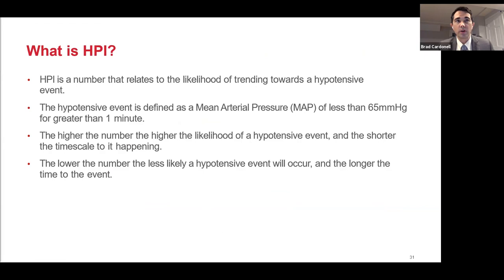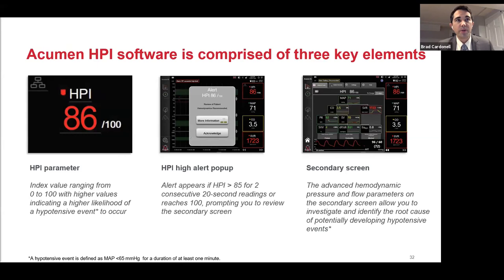HPI is a number that relates to the likelihood of trending towards a hypotensive event, defined as MAP less than 65 for greater than one minute. The higher the number, the more likely the hypotensive event and the shorter the time until it occurs — and conversely, the lower the number, the less likely or the longer until an event. Acumen HPI software has three key elements: the HPI number (a value from 1 to 100), the HPI pop-up alert (which appears after two consecutive readings above 85), and the secondary screen which provides further details about the potential causes and treatments of the hypotensive event — allowing us to get at the root cause rather than just temporizing with vasopressors or unnecessary fluid.